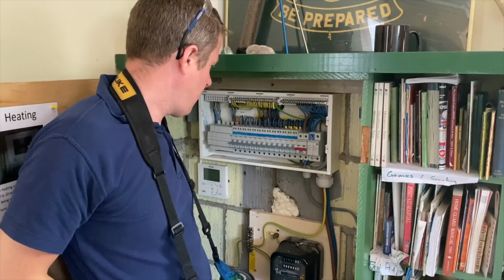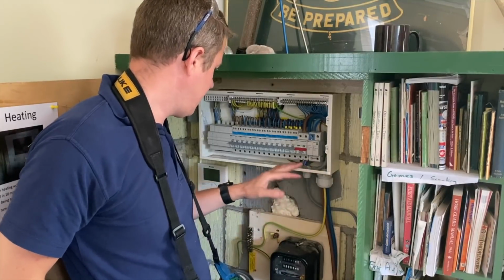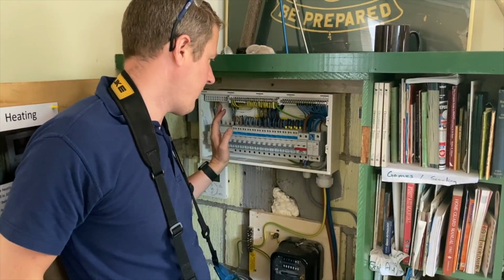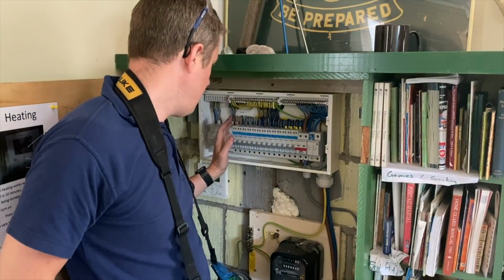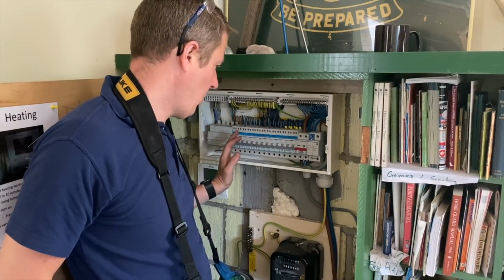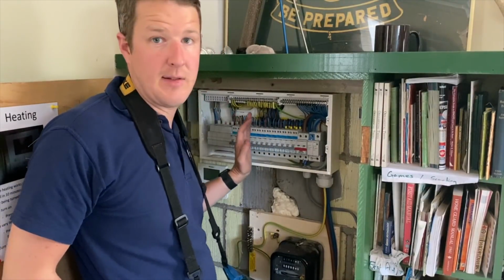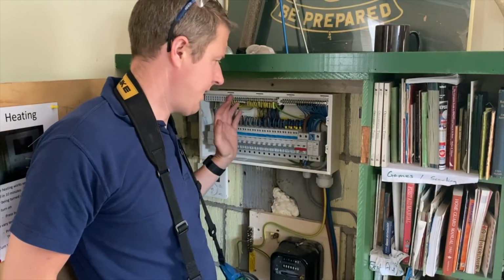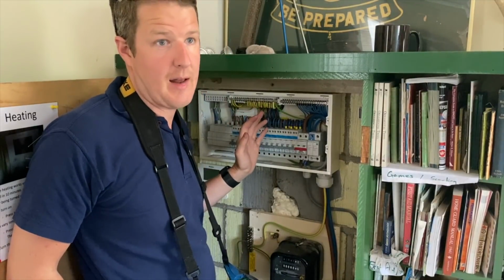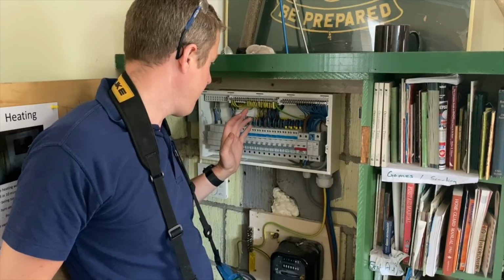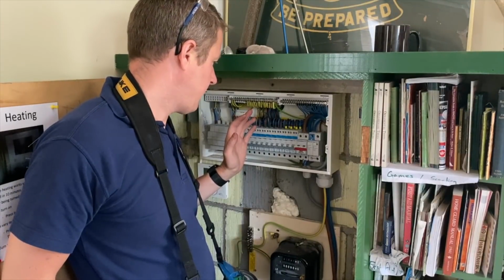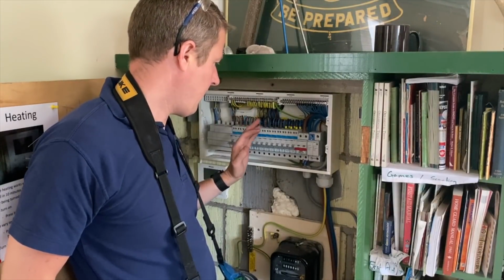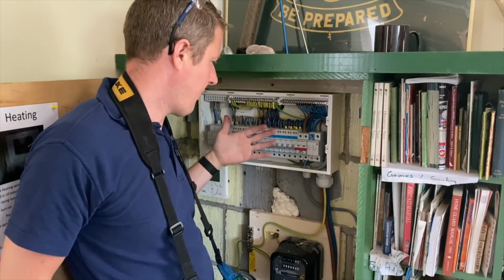Good. So now we've actually completed all the operations that would require us to unscrew anything within the board. The next set of tests is live testing, where we test the earth fault loop impedance at the end point of each circuit. So for that we can actually put the board cover back on.